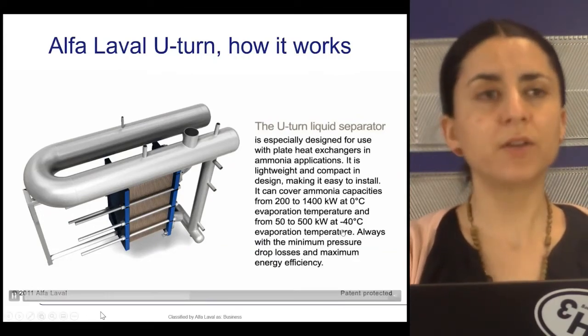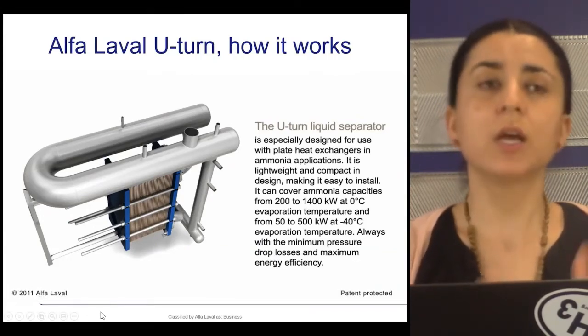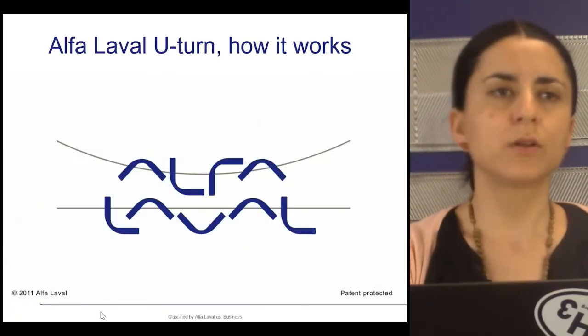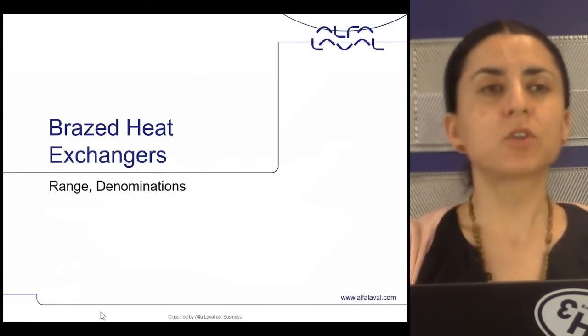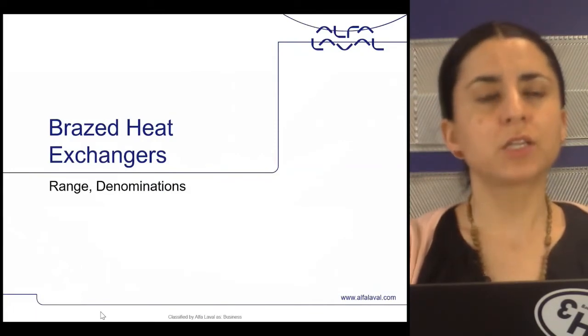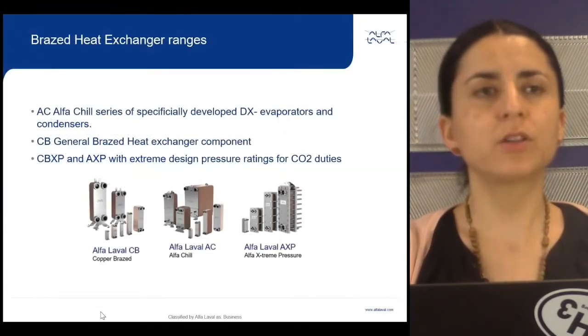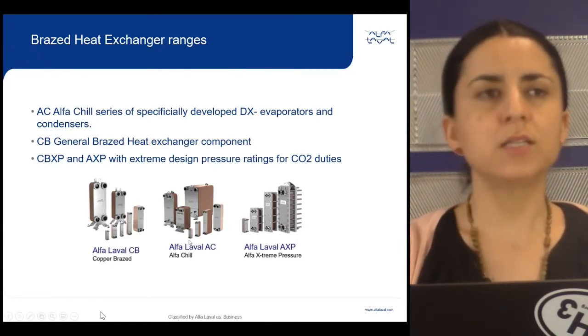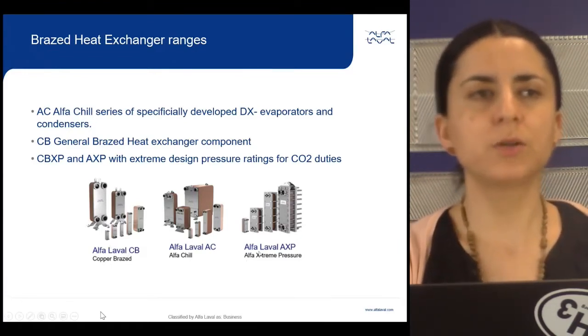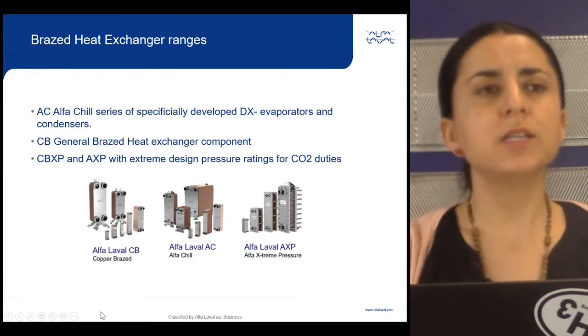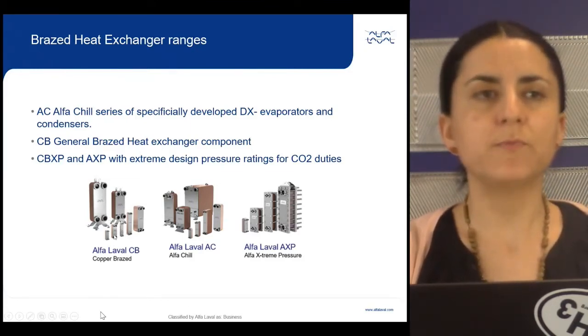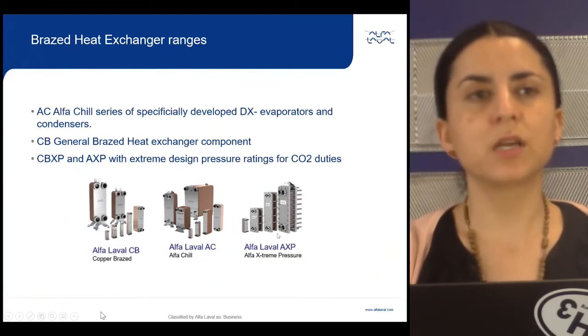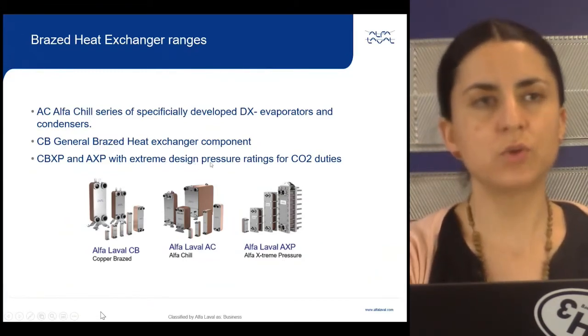Now let's talk briefly about brazed heat exchangers, the range and denominations. We have 3 ranges of heat exchangers. First one is the AC Alfa Chill series that is specifically developed for direct expansion evaporators and condensers. Second one is the CB General Brazed heat exchanger. And the third one is CBXP and AXP that are meant for extreme design pressure ratings for CO2 duties.